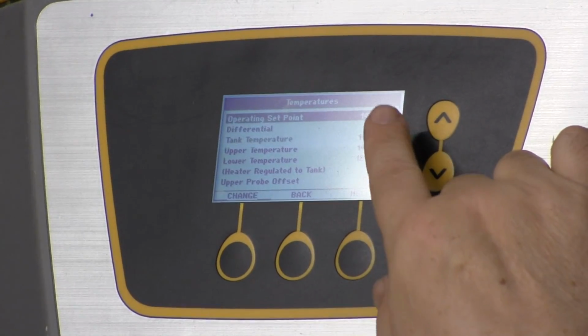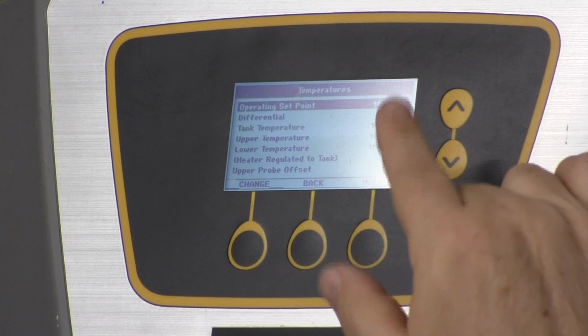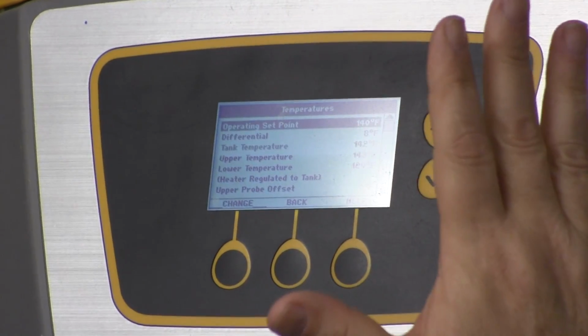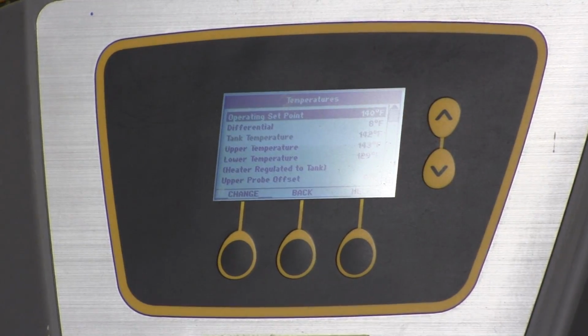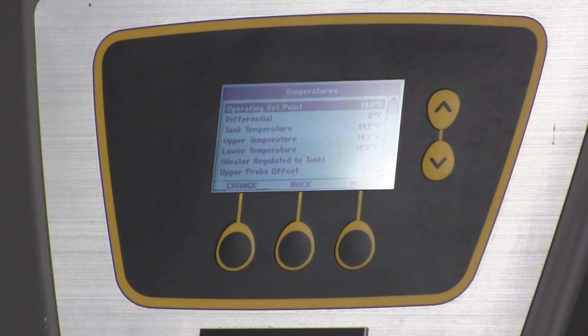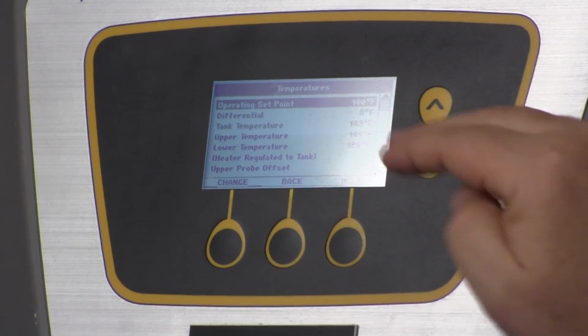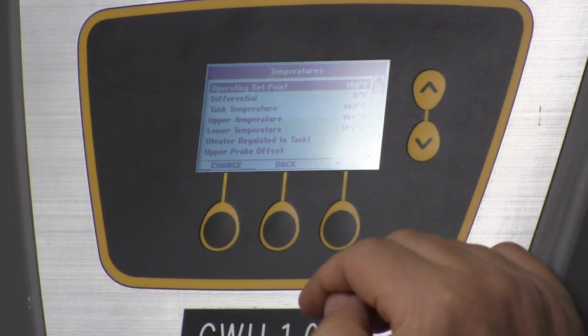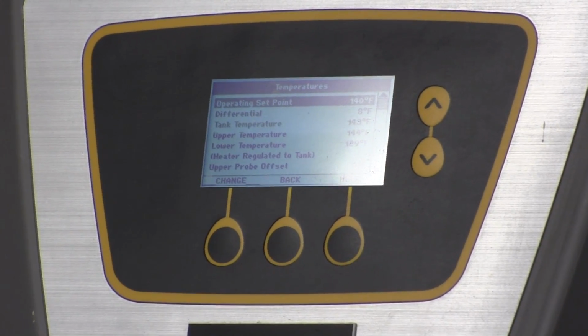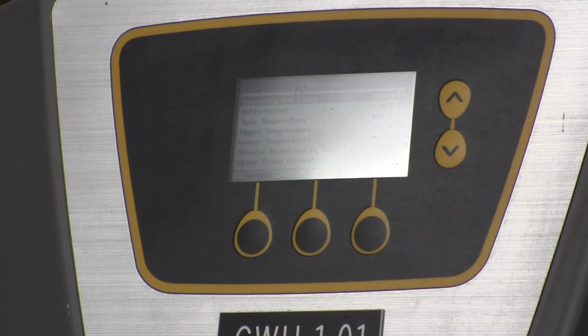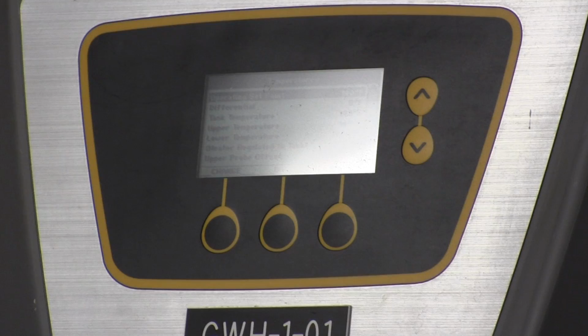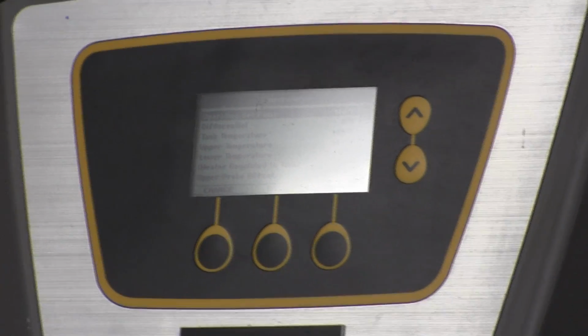The second item on this is the differential. And what that does is it lets you manage how the heaters operate. The differential takes a temperature reading off the top and takes a temperature reading off the bottom. And this is set at 8 degrees. So if this heater reaches 140 and it's satisfied, it's not going to turn back on until it drops 8 degrees. So it really won't fire back up till it's 132 inside that temperature. Depending on your usage, the larger the differential you can get away with, the less the controls actually have to go off and on. I mean, they're tested at 5 million cycles or 500,000 cycles.